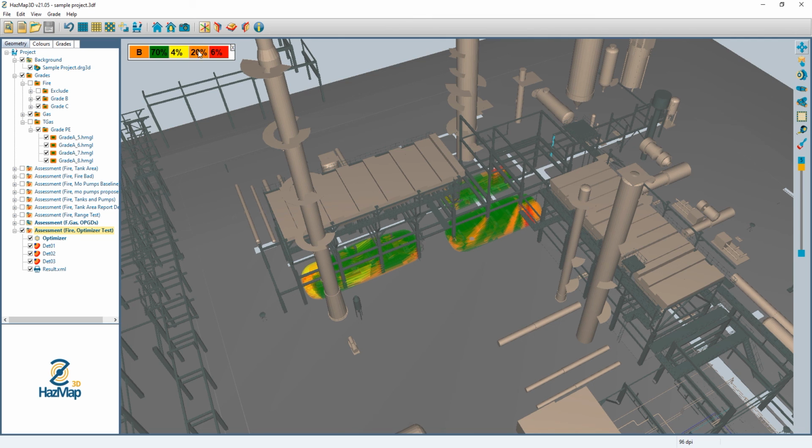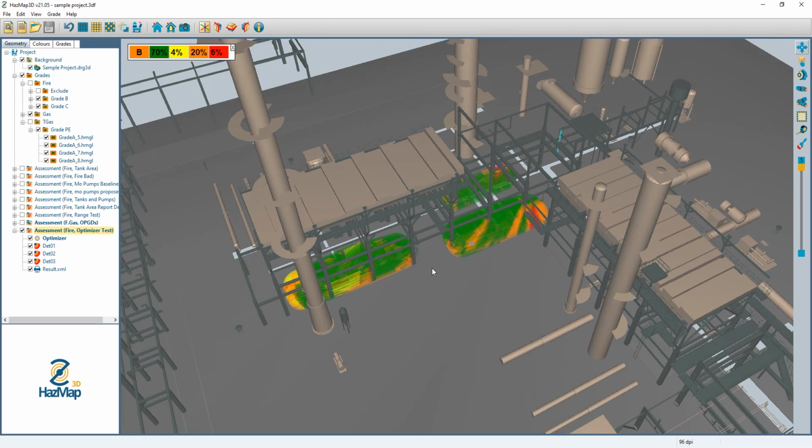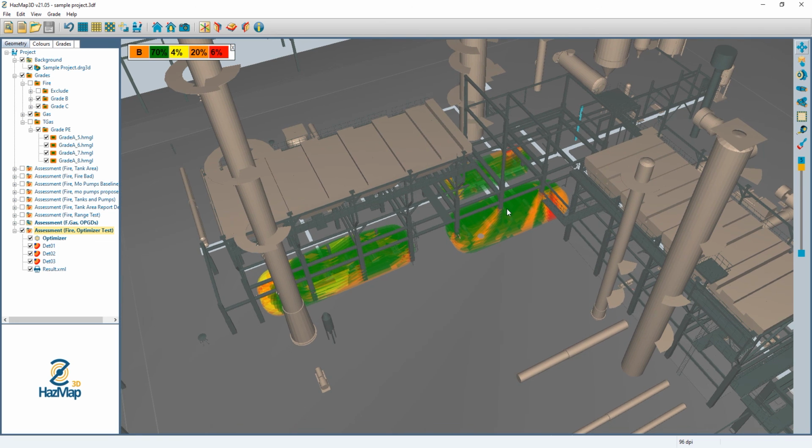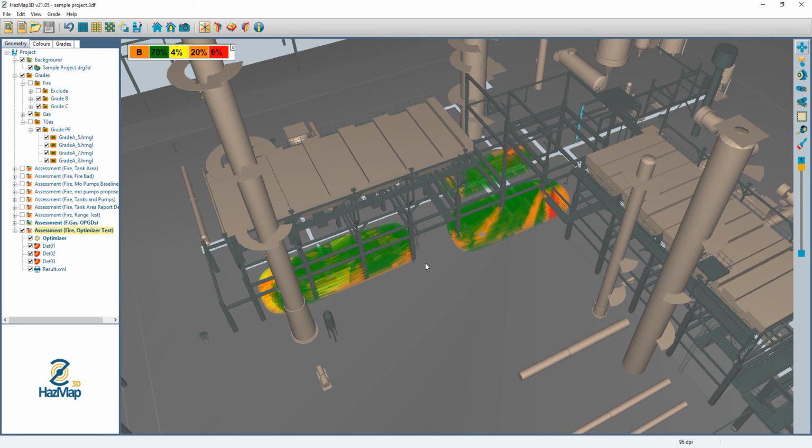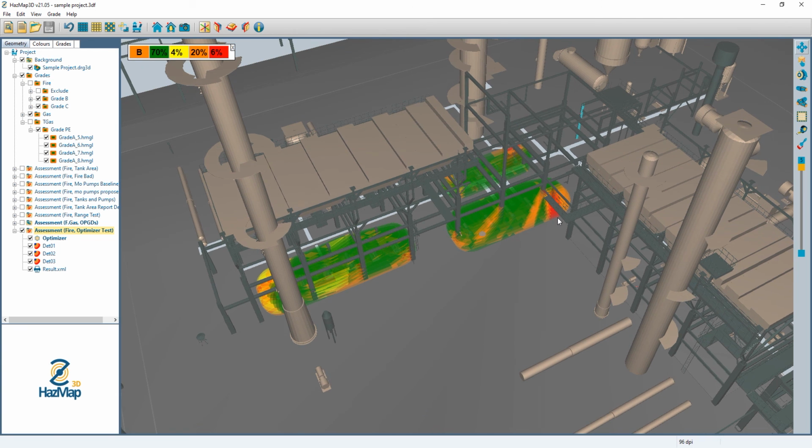And of course I didn't change that much, so I'm seeing slightly lower 2 out of n coverage, but it didn't really change the results much. But that way I have the detector programmed in a location that's a little bit more favorable, a little bit more realistic, because you're not going to just put a post anywhere. And so that is a brief demonstration of the Detector Optimizer tool.